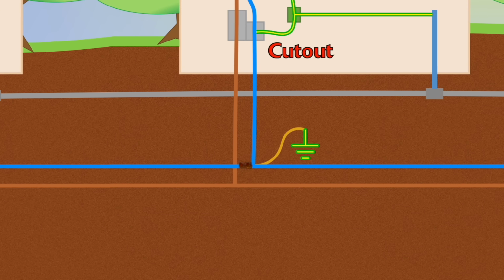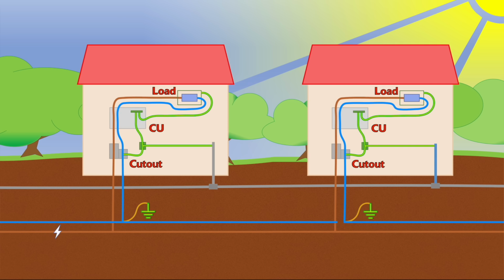Now, the neutral current from property A can't divert through the incoming plastic pipe, so it flows down the neutral as expected, but because it can't get back to the transformer, some of it will go through the general mass of Earth via the PME as it should do. However, as this metal pipe is buried in the ground and connected to the general mass of Earth along potentially a long distance, that means it could present as good a path, if not better, back to the transformer, and therefore a chunk of the current could flow along there as well, giving us diverted neutral current back through the earthing arrangement.